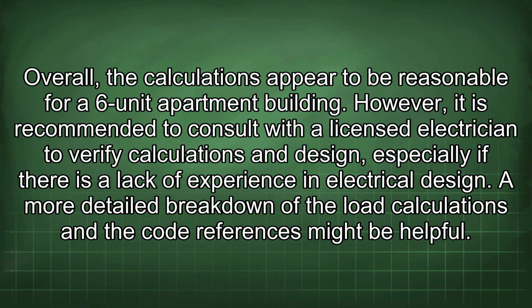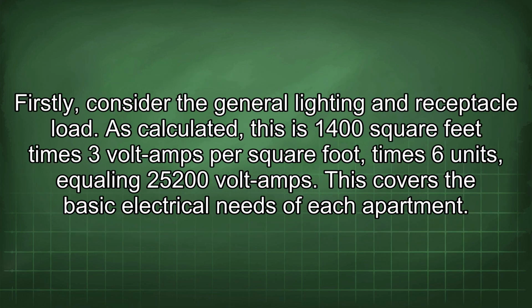A more detailed breakdown of the load calculations and the code references might be helpful. Firstly, consider the general lighting and receptacle load. As calculated, this is 1400 square feet times 3 volt amps per square foot times 6 units, equaling 25,200 volt amps. This covers the basic electrical needs of each apartment.